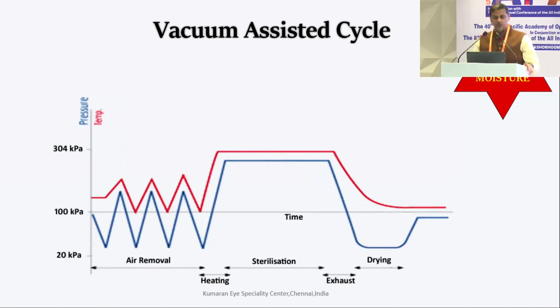So how do you decide what load you want? First, the most important thing is the water source, because only if you have a proper water source can you get a saturated steam. Remember, the steam should not be hypersaturated or hyposaturated, which could decrease the efficiency of sterilization. So what is saturated steam? 3 to 5% of moisture. So this will help you to understand the process.